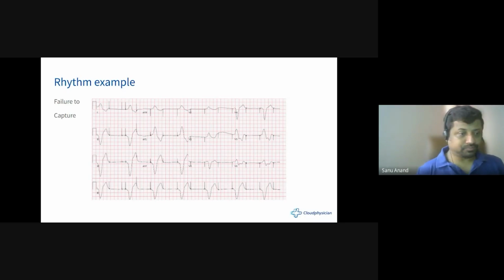Failure to capture. Failure to capture means the ventricle is sensing fine. The ventricle is also putting out an impulse, but the impulse that the pacer has put out has not caused a myocardial depolarization. So the ventricle is sensing fine. It is pacing fine. So the pulse generator is working okay. The sensing part of the lead is working okay. But somehow there is failure to capture.